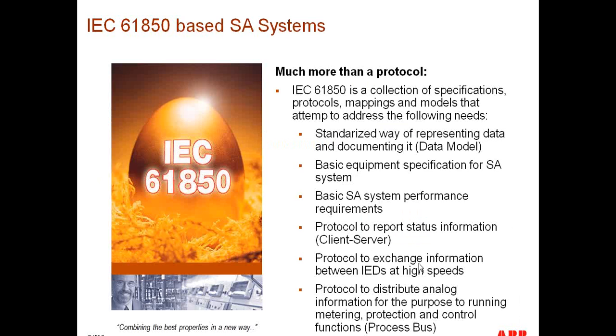We also define a protocol to exchange information between relays at high speeds, and this is GOOSE messages, the capability to exchange binary, analog, and counter information from one relay to the other in high-speed fashion.